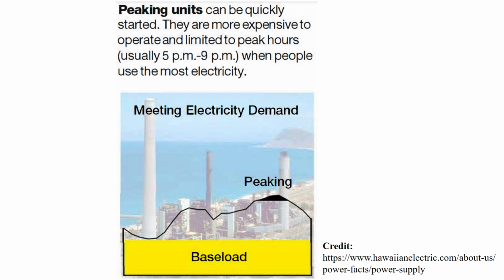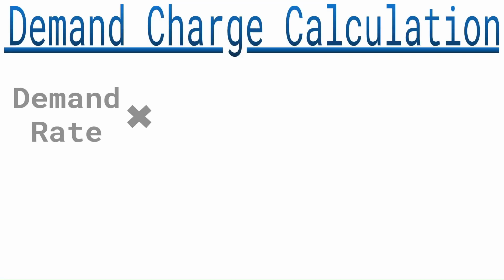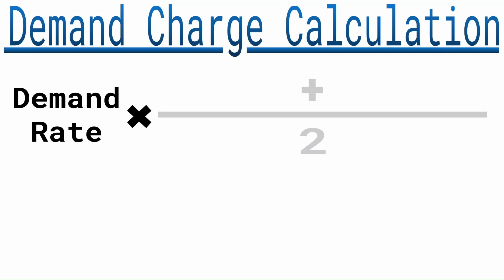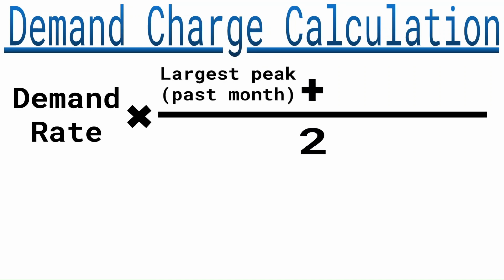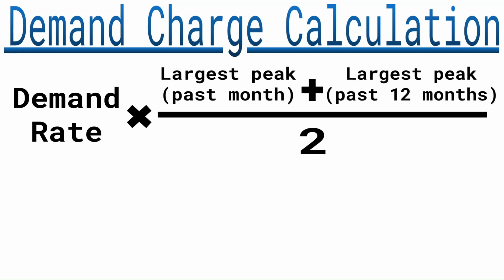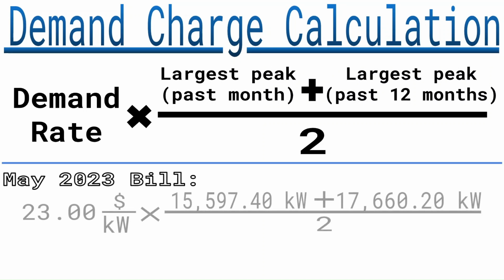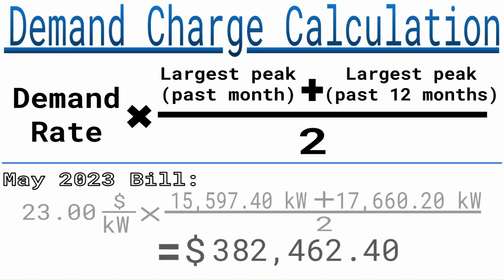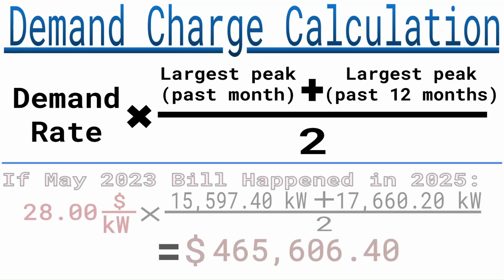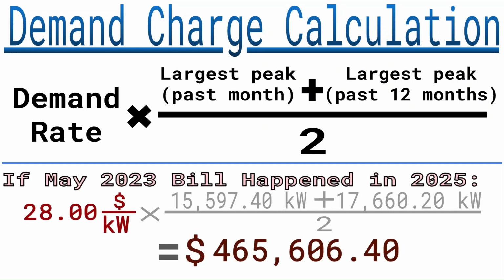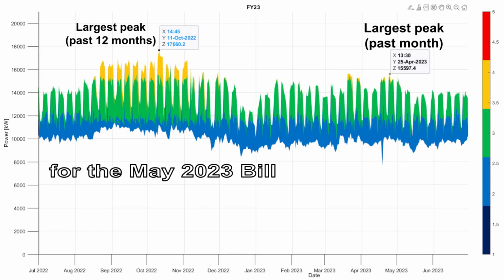The demand charge is calculated by multiplying the demand rate, set by HECO, by the average of the peak demand of the month and the peak demand over the previous 12 months. In early 2023, the demand rate was $23 per kilowatt. In 2025, it is now $28 per kilowatt. If we were in the same situation as we were 2 years ago, we would be paying almost $500,000 on this charge alone for every billing.